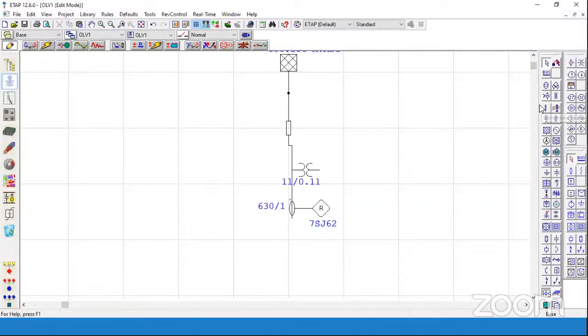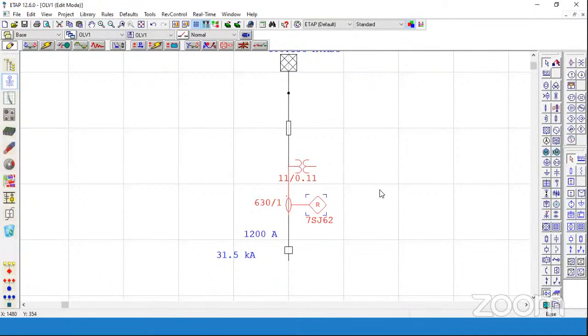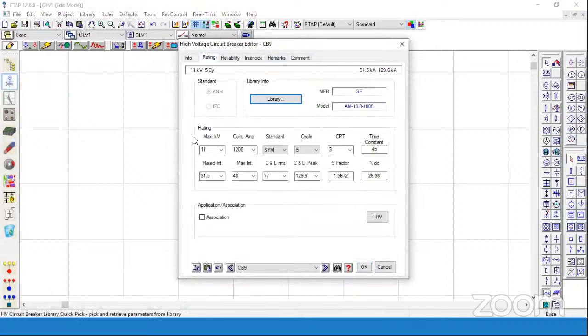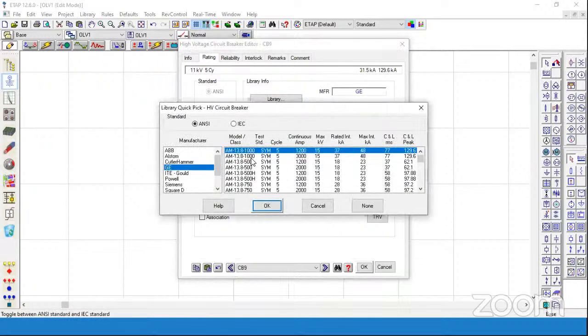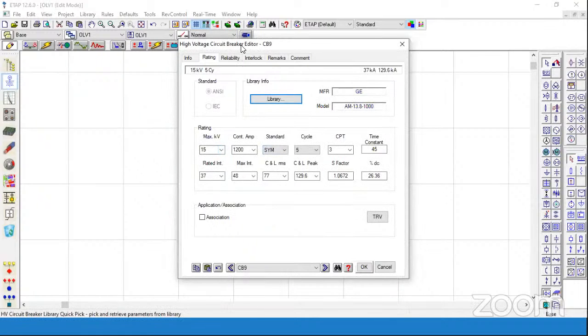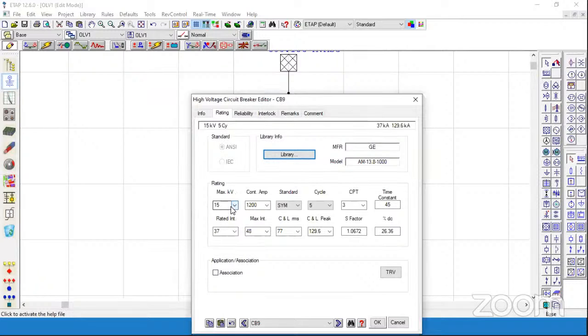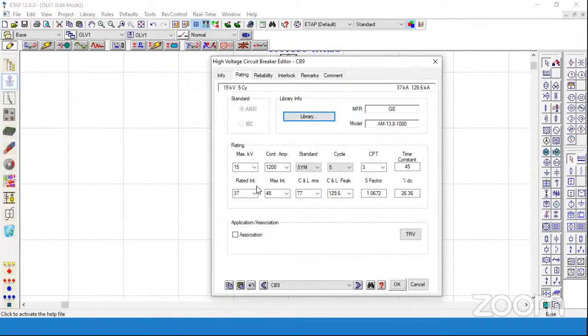Then we will have a circuit breaker. The circuit breaker can be of different makes. We can say General Electric make, ABB, Alstom, Siemens. Let's go with a General Electric make. Here you can see, as the system is 11 kV, the maximum voltage will go up to 15 kV as per the library which we have selected. The continuous ampere rating of the circuit breaker will be 1200 ampere. The breaking capacity of the circuit breaker will be 37, or we can set it as per our details. We can also set other parameters which actually exist in our circuit breakers. So let's take a 50 kiloampere circuit breaker.